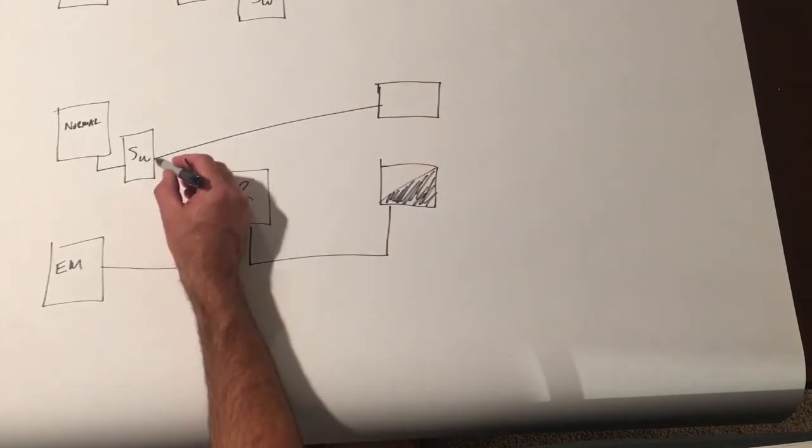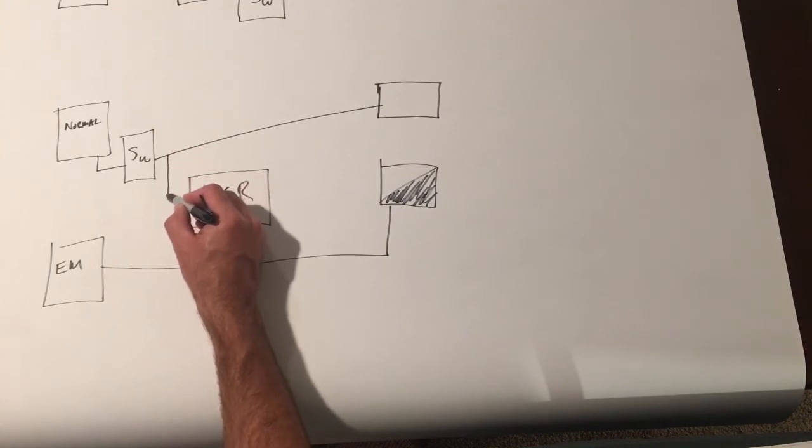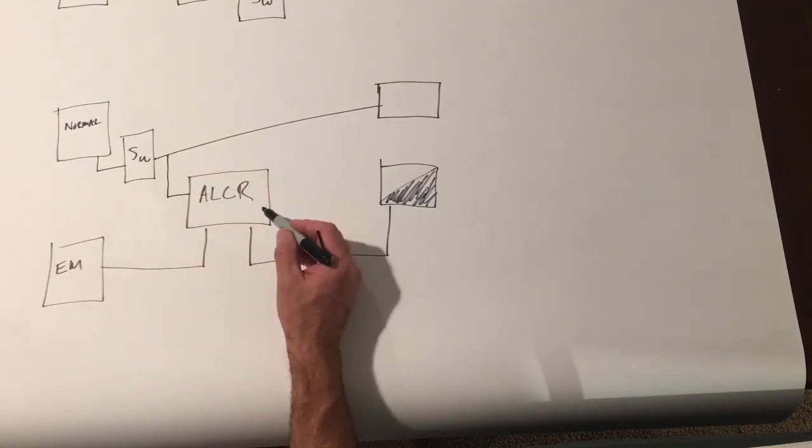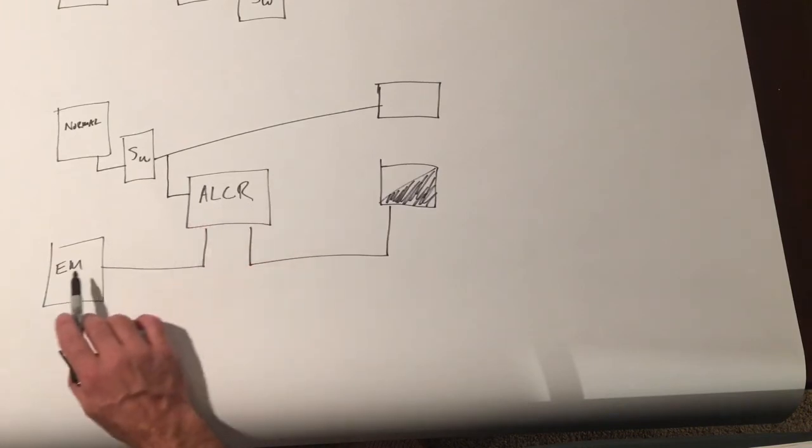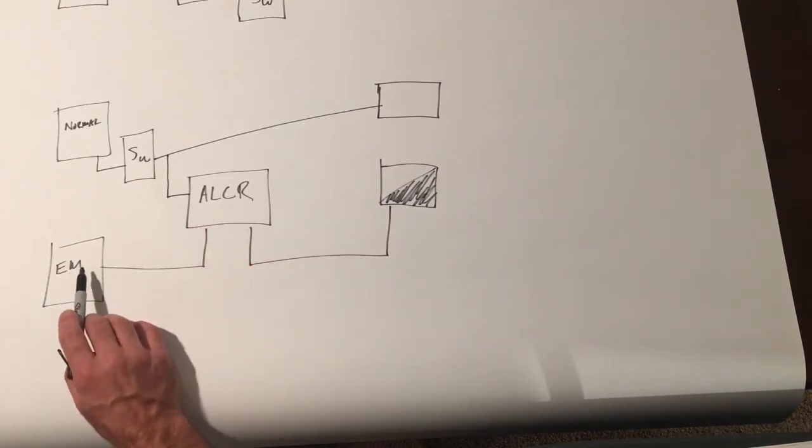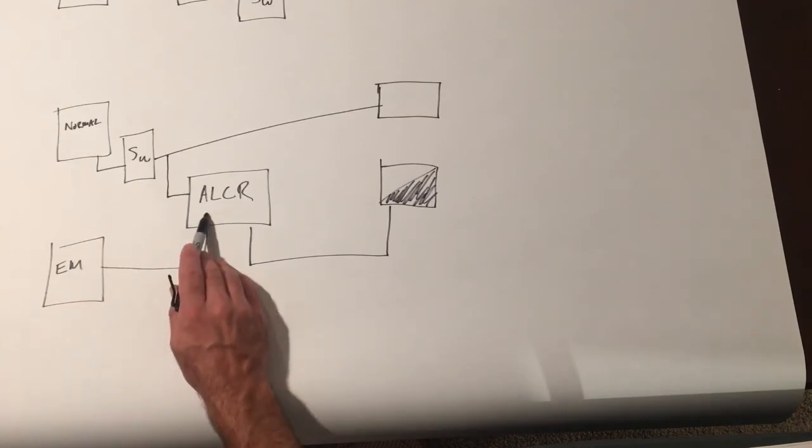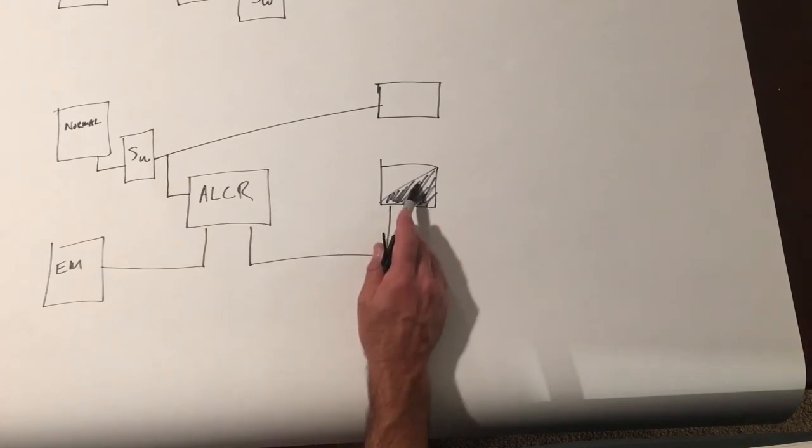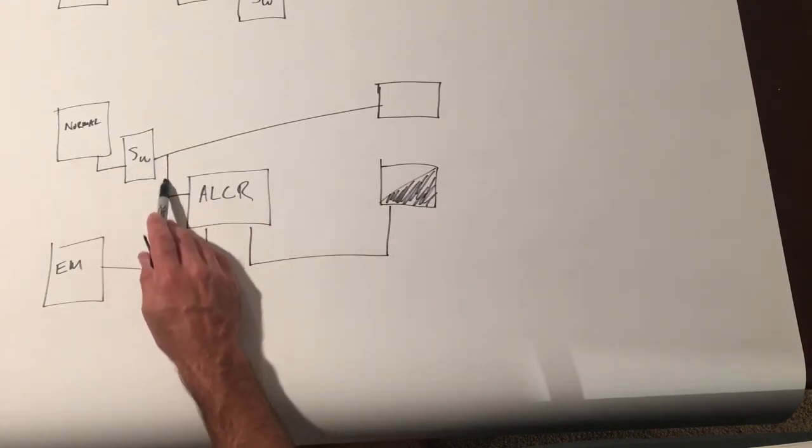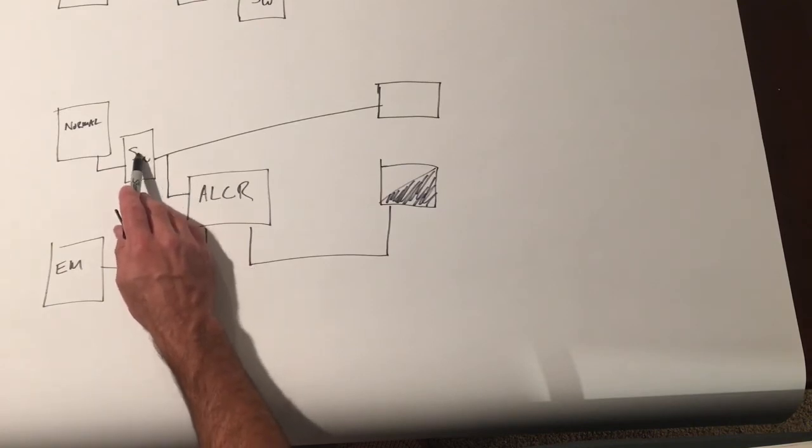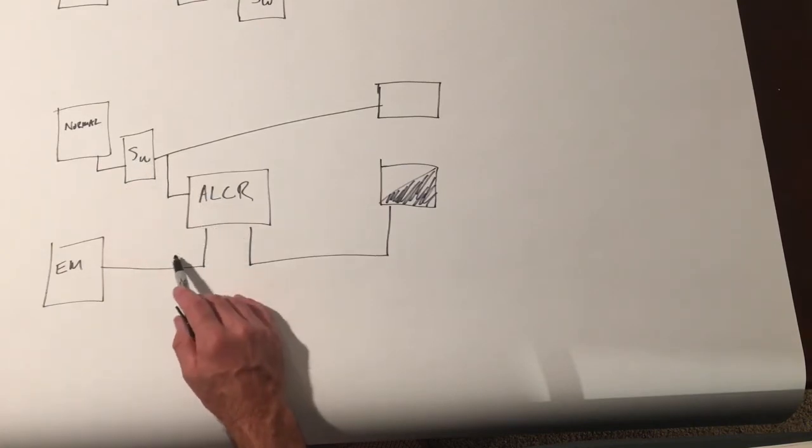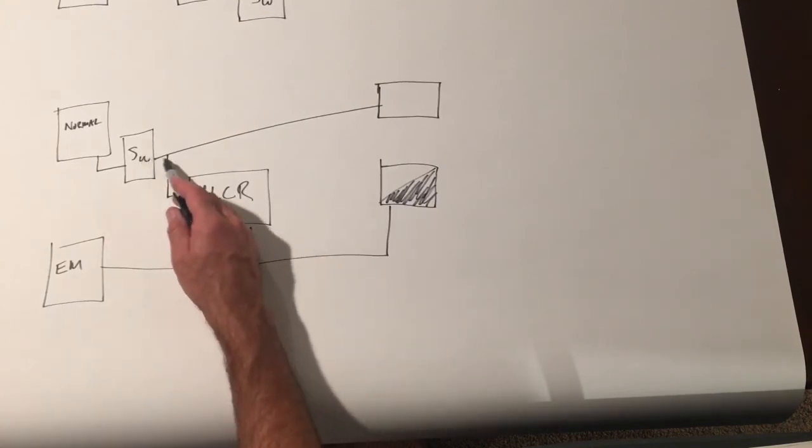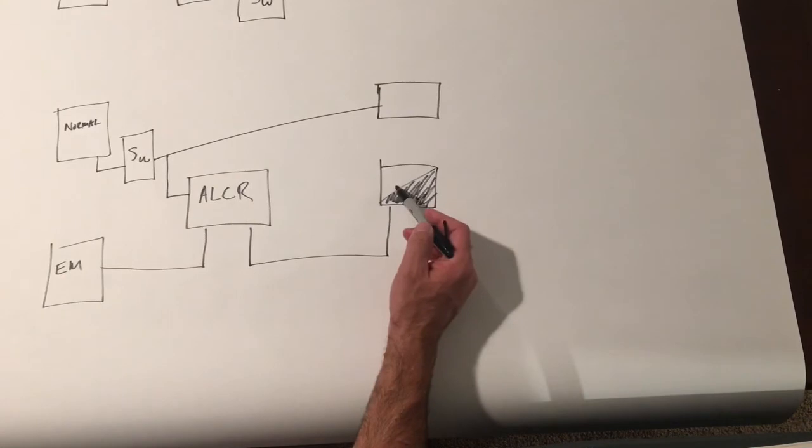But also from the switch, from that switch normal output, we're going to come out of the automatic load control relay. And this is the one tricky part of this that I want to show you so it makes you understand. So in this case, emergency power comes here into the automatic load control relay and goes out to this fixture. This is normal power going into the switch coming into here. So this switch is actually telling the power how to flow through here. So if the switch is on, power flows through here, lights on.